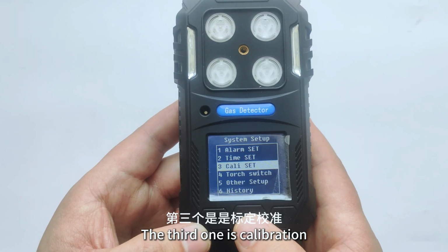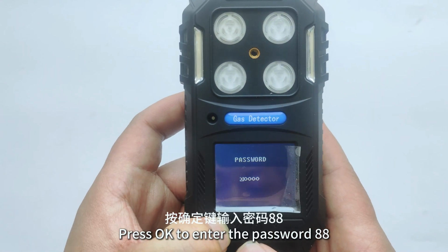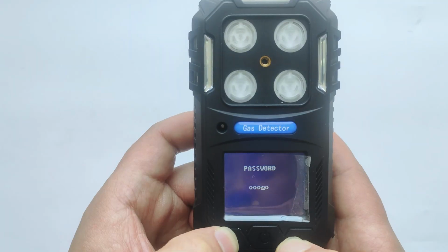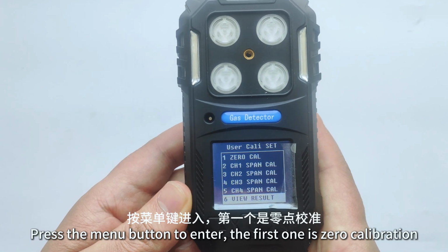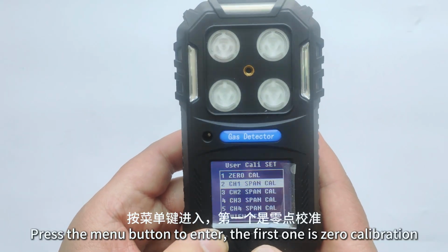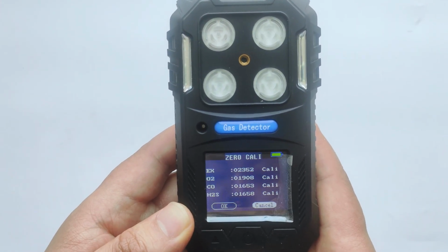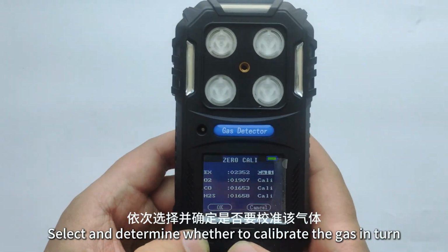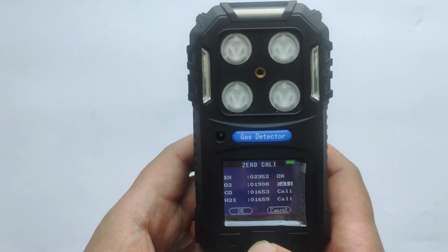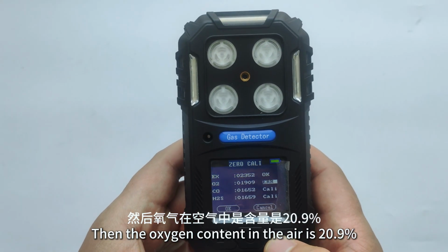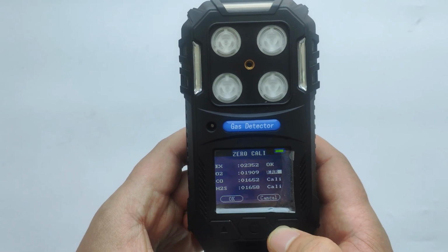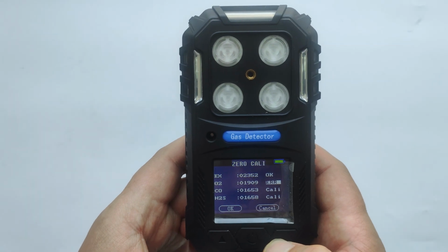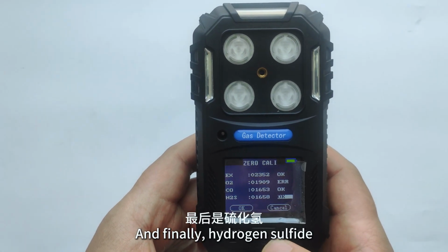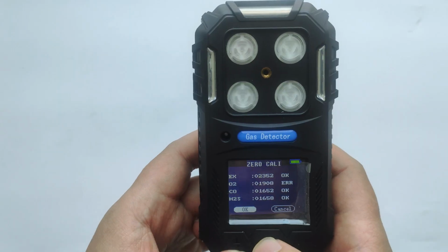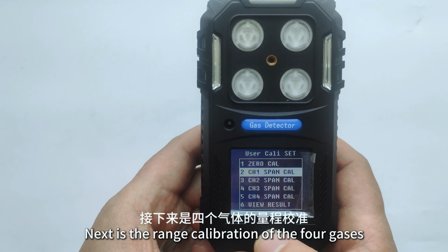The third one is calibration. Press OK to enter the password 88. Press the menu button to enter. The first one is zero calibration. Select and determine whether to calibrate the gas in turn. Then the oxygen content in the air is 20.9%. So the calibration succeeded. And then carbon monoxide. And finally, hydrogen sulfide. Next is the range calibration of the 4 gases.